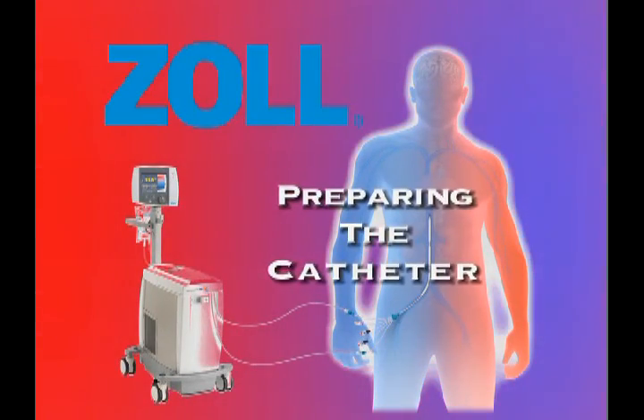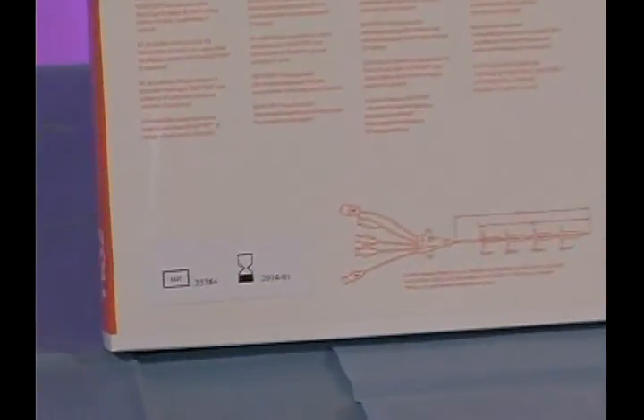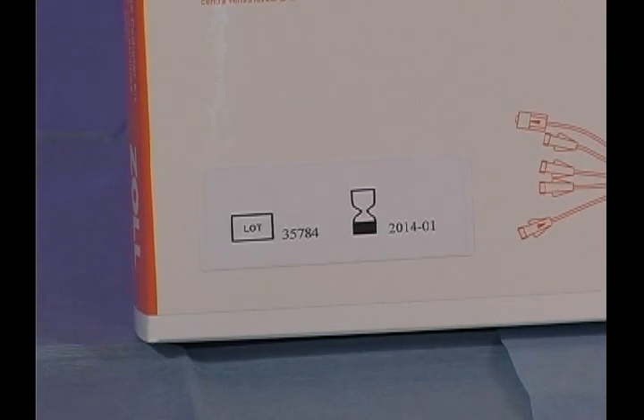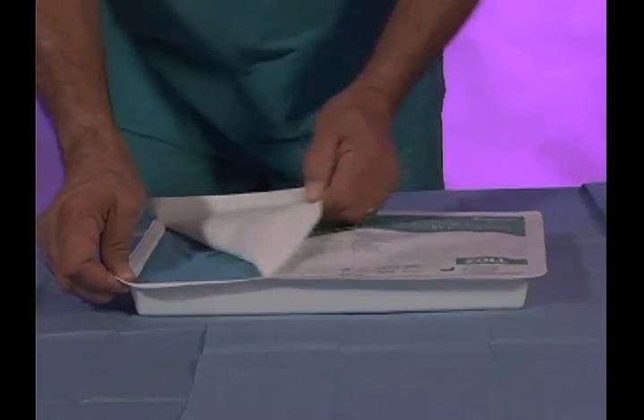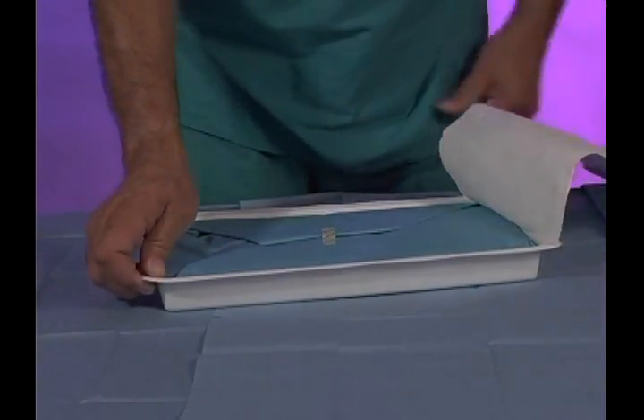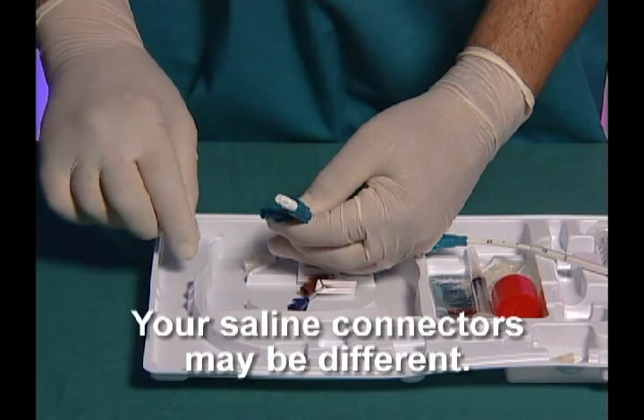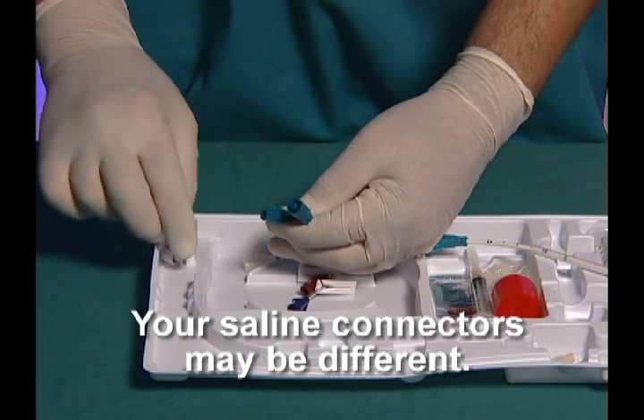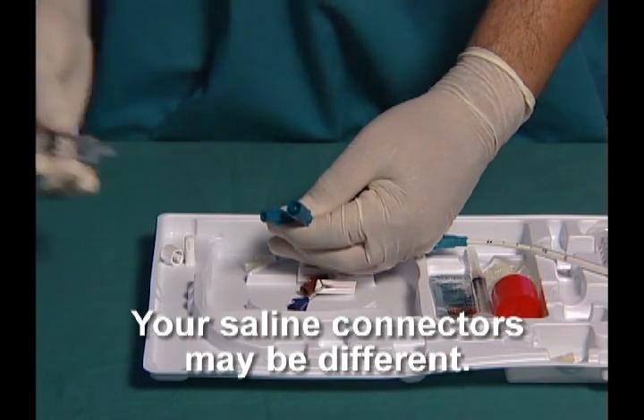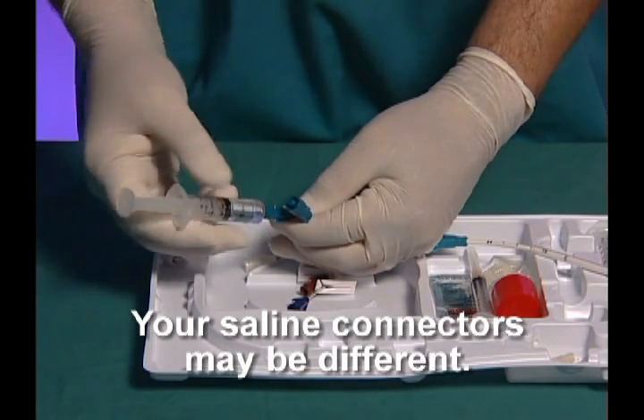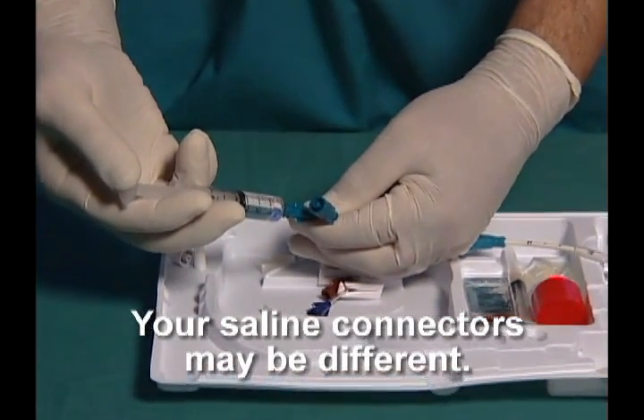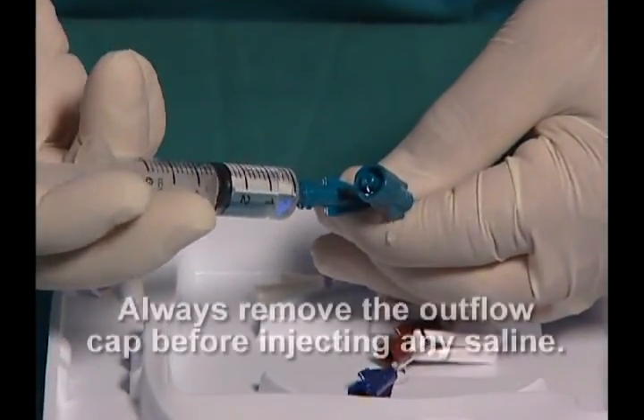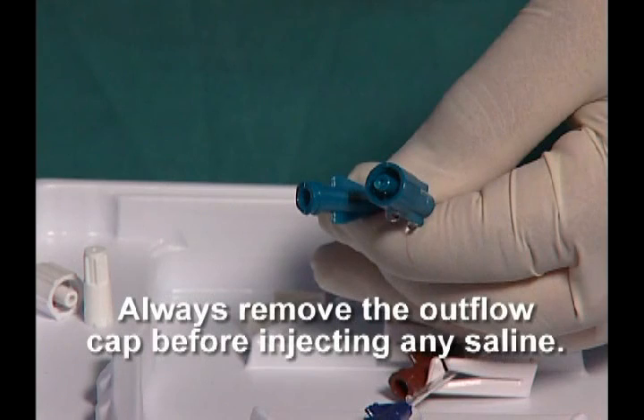Preparing the catheter. To begin, please check the expiration date on the catheter package. Then, open the tray and remove the Zoll heat exchange catheter. Keeping the balloon cover in place, remove the 2 caps from the saline inflow and outflow luer hubs. Slowly inject sterile saline through the inflow luer until it begins to exit the outflow luer. It's important to always remove the outflow cap before injecting any saline.